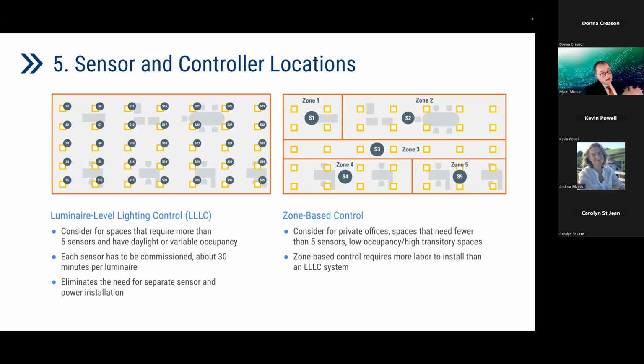Again, many of the luminaire level products out there are combined daylight and occupancy sensors. The advantage to this is you don't have to worry about it as much in the design phase. You can just lay out all the fixtures in the space, and then when you get into the space, you can say, yes, I want the first two rows connected to dim at this rate from the daylight sensor, but rows three and four to dim at a lower light level because they're not getting as much daylight, and maybe the fifth row gets no daylight dimming because it's not getting any daylight.